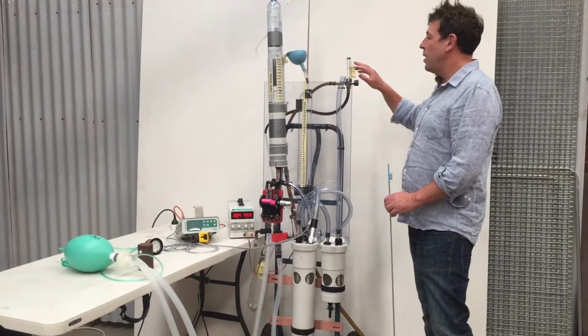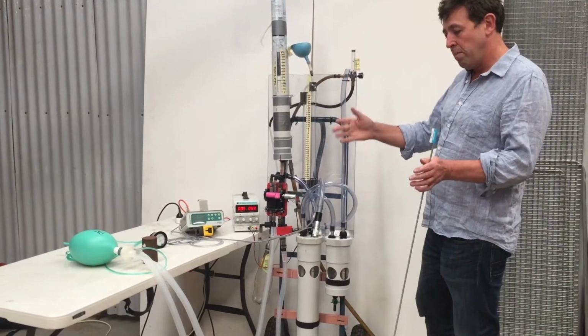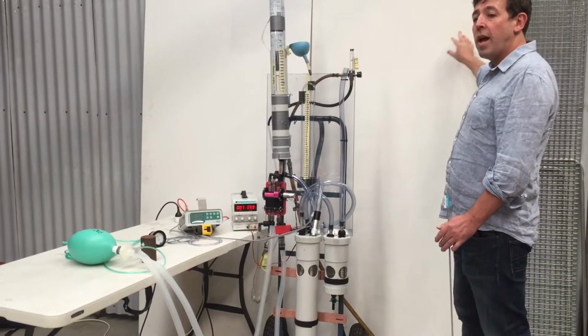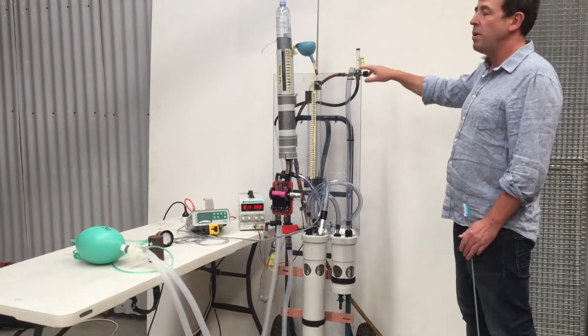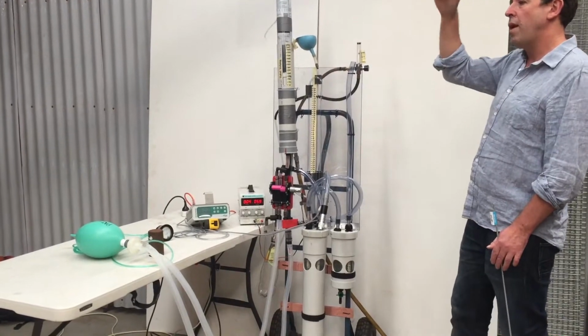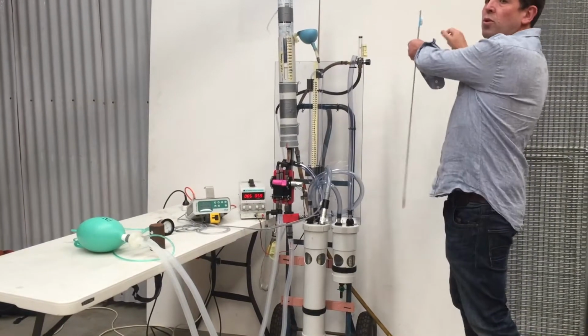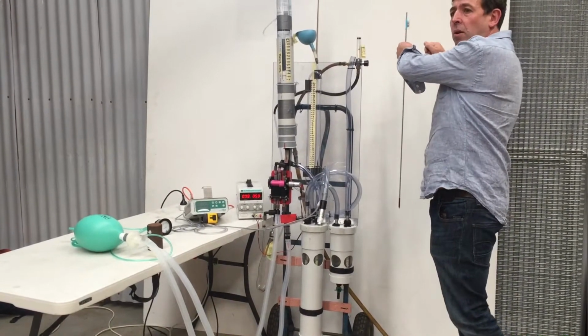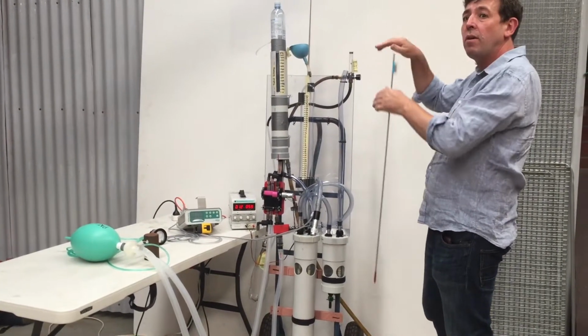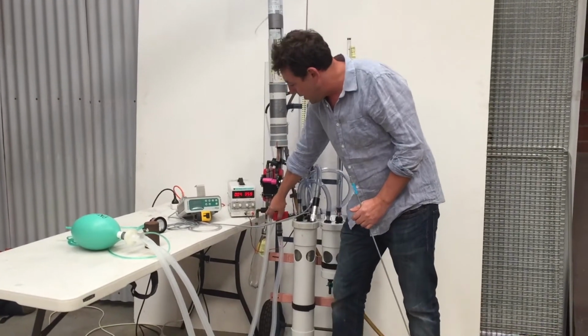but essentially what I imagine is in a normal hospital bedroom, there'll be on the wall piped oxygen and air supply, and on those will be flow meters similar to this one. And so those flow meters drop the 4 atmosphere pressure in the hospital wall down to something a bit more usable. So we'll have an oxygen and an air supply. That's really handy because you can adjust the relative blends of those to vary how much oxygen the patient gets. That feeds into this little system here.